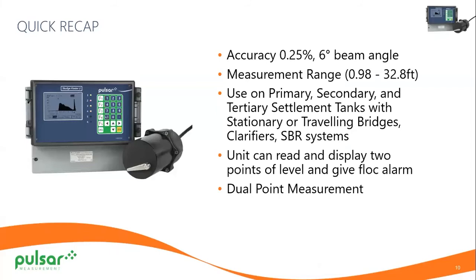Quick recap. Accuracy, 0.25%, 6-degree beam angle. We have an almost 33-foot range, and we have about a 1-foot blanking distance. The combo gets used on primary, secondary, and tertiary settlement tanks with stationary or traveling bridges, SBR systems.